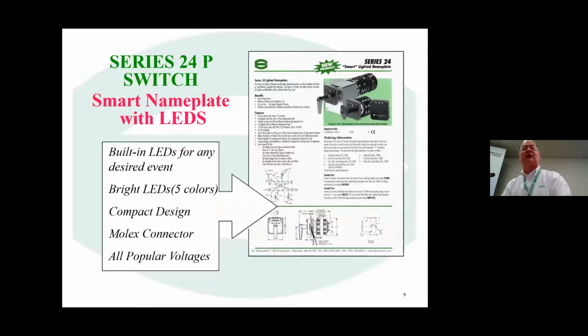One of the things that we've also done with this particular line is to incorporate the LEDs, the lighted nameplate LEDs, that allow control switches to be local annunciators, as well as electronics that could have an output that could give me a SCADA contact in the nameplate area. So we have typical LED configurations with 5 colors: red, green, blue, white, and amber. And that allows you to not have to have a separately wired annunciator light panel.